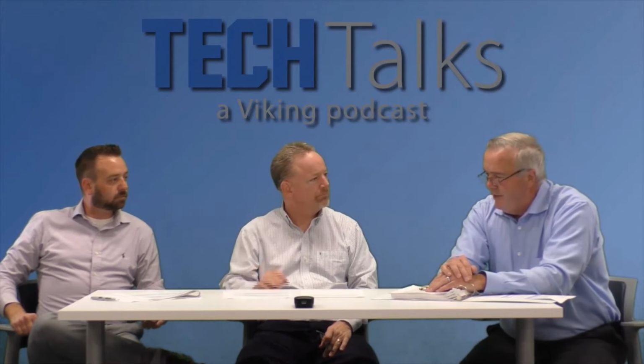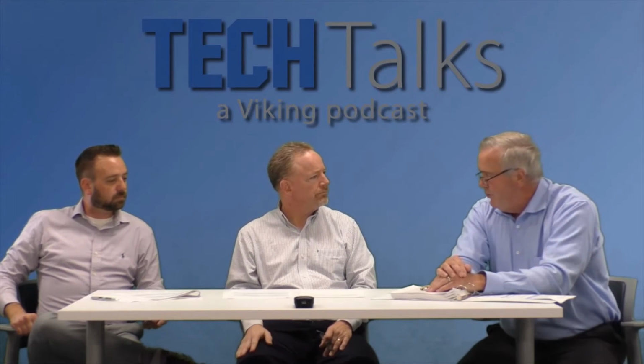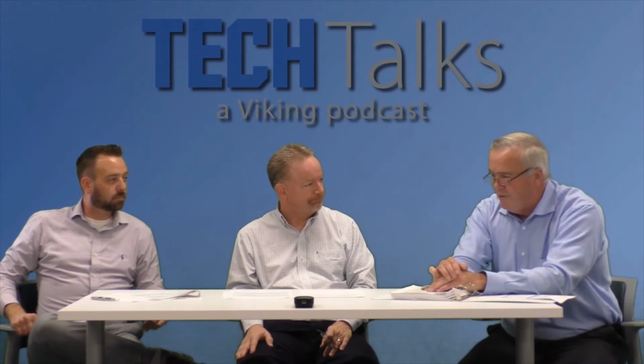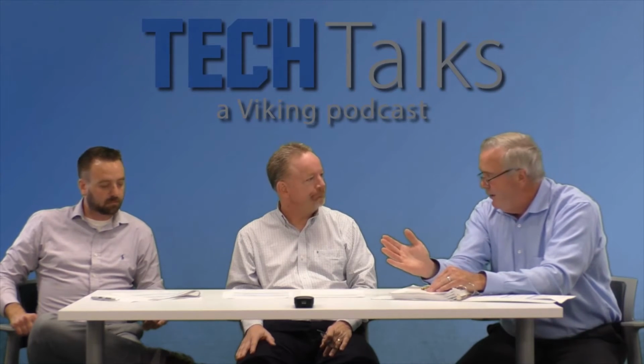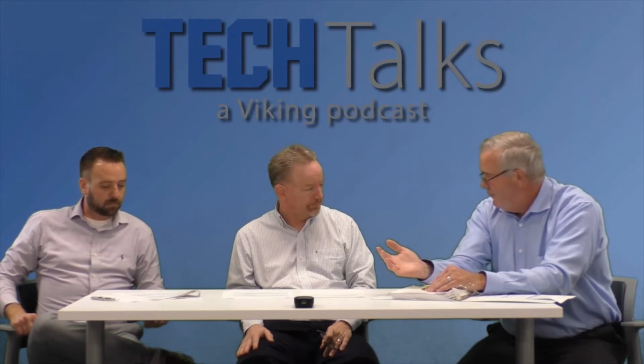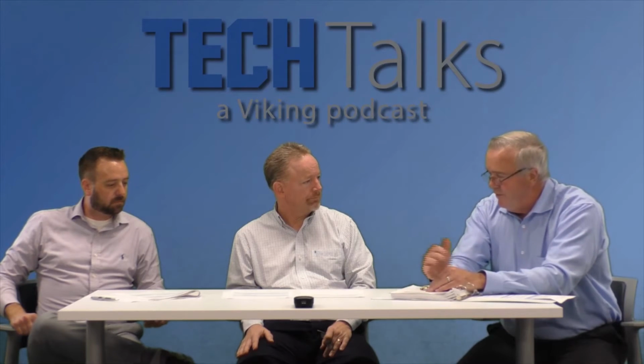that, hey, I had somebody enforce 3-0 on me, and I had to go to 5 sprinklers on a branch line. And for those of us who do hydraulics, you know how much of an impact going to that 5th sprinkler on the branch line can be. And that could be the difference between 2 to 2.5 or 2.5 to 3 on branch lines, just because you didn't really understand that 3-0 required this formula for how many sprinklers are going to be calculated on a branch line.